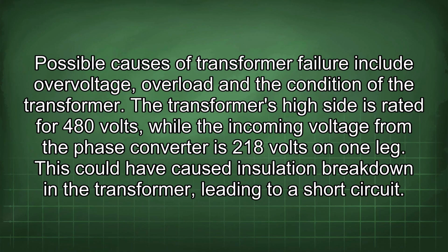Possible causes of transformer failure include overvoltage, overload, and the condition of the transformer. The transformer's high side is rated for 480 volts, while the incoming voltage from the phase converter is 218 volts on one leg. This could have caused insulation breakdown in the transformer, leading to a short circuit.